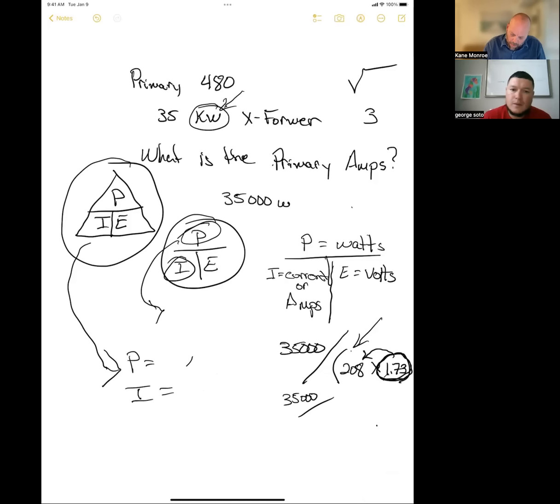You know what? Let's work on this right here. Let me show you this one. What we're going to do is take 208 right here. Sorry, you can't see what I'm pointing at. 208 right there and multiply it times 1.73 and it's 359.8 or something. We can round it up to 360 and then take that 35,000 divided by 360 equals 97.2, and that's your secondary side amperage.